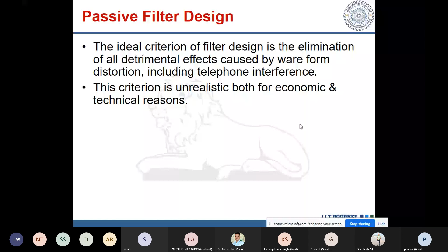One of the problems with the passive filter is that the filter is in parallel with the load, and it also comes in parallel with the source. It means the harmonic current injected by the load should ideally be completely absorbed by the filter. But the filter does not exhibit zero impedance corresponding to that harmonic. So if you see the filter from the load side, the filter is in parallel with the source, and therefore this harmonic current is divided between the source and the filter.